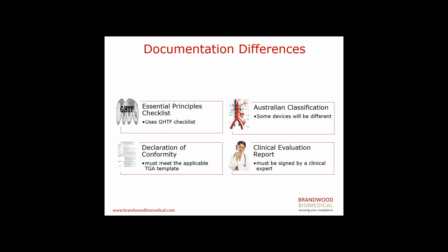And lastly, it's the Clinical Evaluation Report. In Australia, it is a requirement that the report be written or at least endorsed by a clinical expert. As opposed to this, we have also noticed, just in our experience when handling these applications, that TGA is quite picky about the presentation of their clinical evidence report.